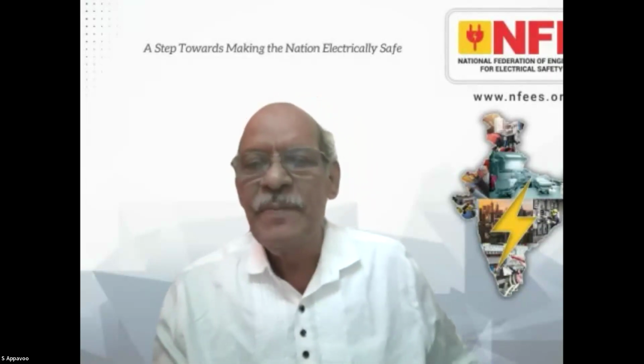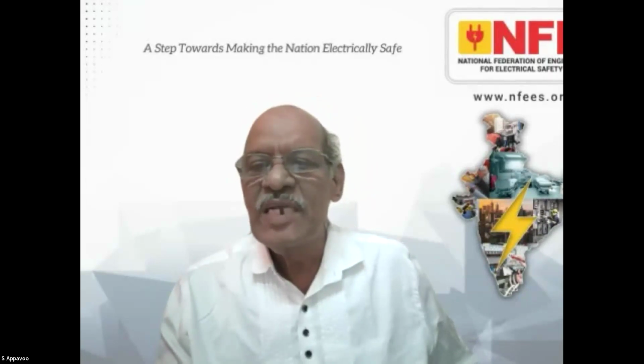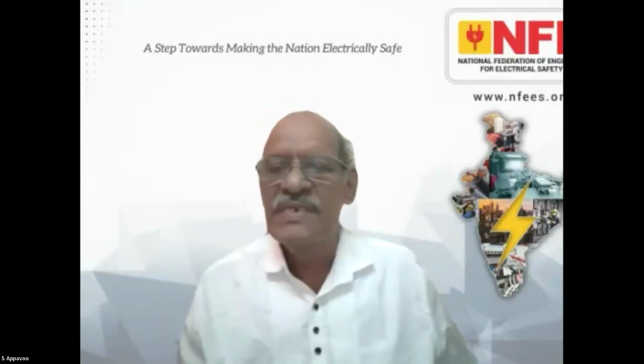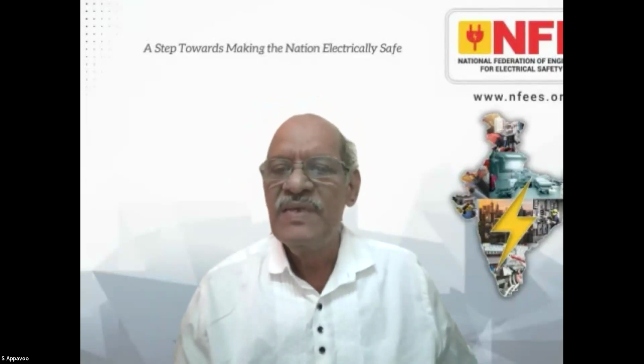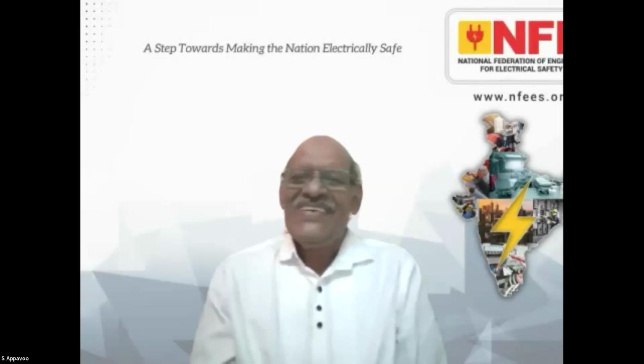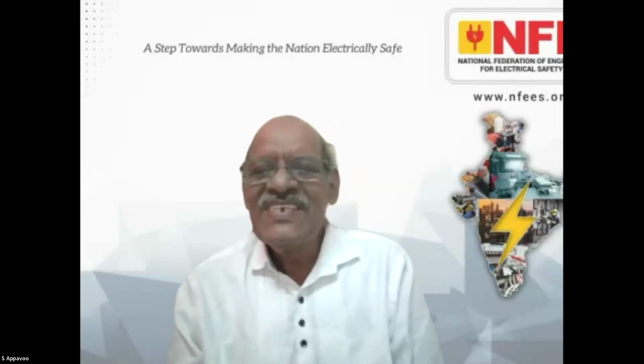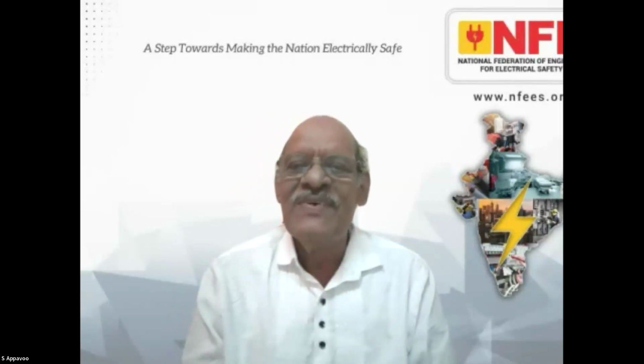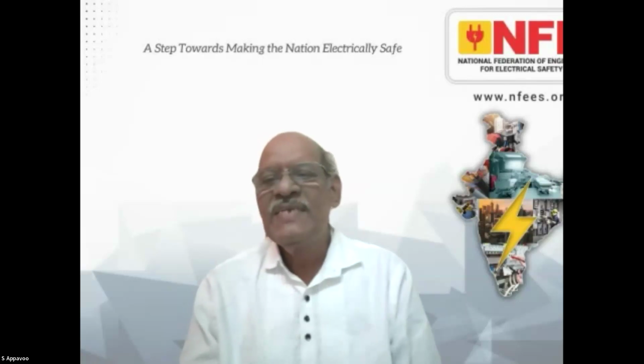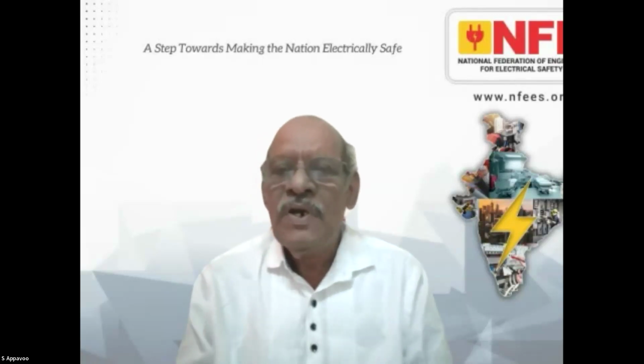Another question is from Satya P: what type of lightning arrestor is recommended for malls and shopping centers? Actually, I don't know about a lightning arrestor. If you mean a rod, then the normal IEC 62305 standard is recommended. Lightning protection is not separate for a mall or a shopping center. It is for the building, as explained in 62305 Part 3.